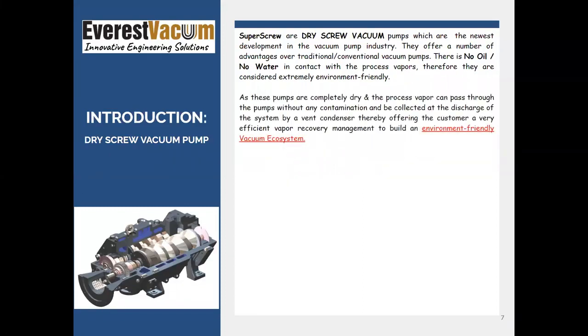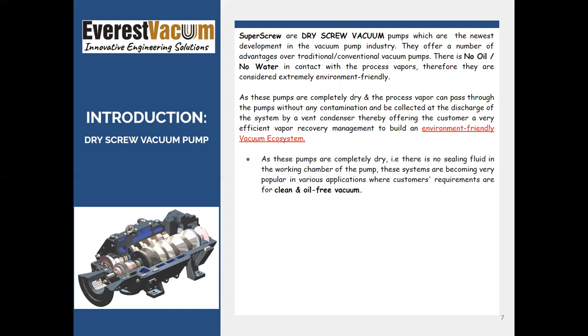As these are completely dry pumps, the advantage is that they can directly handle the process vapors, and these can be collected at the discharge by a condenser. It is much easier to have condensation at the discharge. So we can condense the process vapors entering the pump, and this leads to a very efficient vapor recovery management system and ultimately creates an environment-friendly vacuum ecosystem. As these pumps are completely dry, there is no sealing fluid inside, so they offer clean and oil-free vacuum levels.